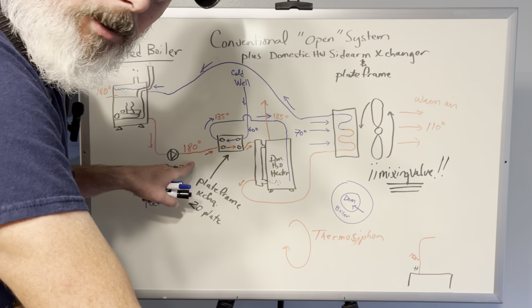So you must, I'm going to tell you, you must have a mixing valve. Don't not put one in because, oh, we'll just know that we've got to be careful. Do not do this without a mixing valve. And a three-way mixing valve, basically, this would be cold from the house. I sure hope this is showing up on camera. That would be cold water from your house. That's going to be hot water from the boiler, well, actually from your water heater, sorry. And this is going to go out to your fixtures.